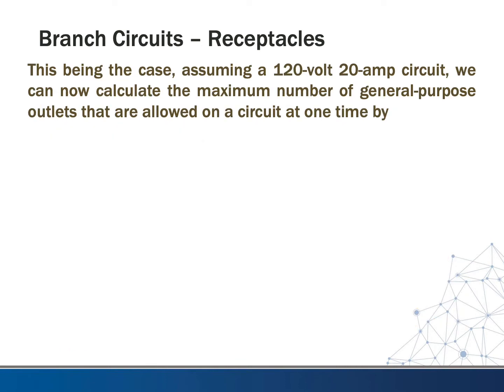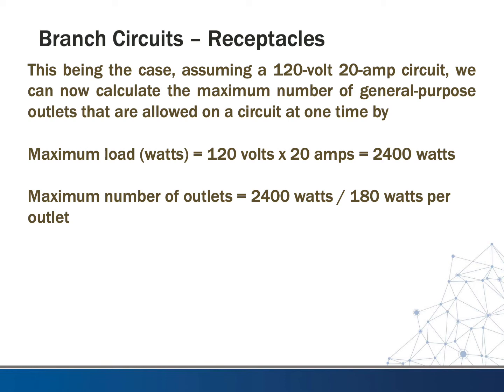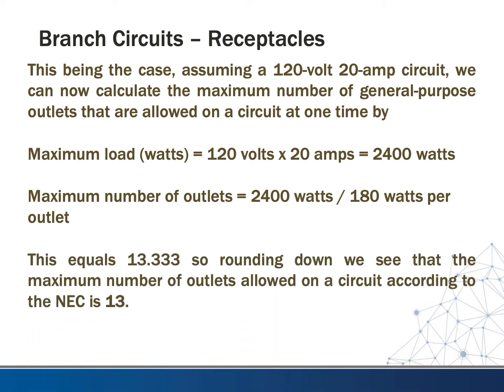Assuming a 120-volt, 20-amp circuit, we can calculate the maximum number of general purpose outlets allowed on a circuit. The maximum load on a 20-amp breaker is 2,400 watts. Since these are non-continuous, we can use the full rating of the breaker. Dividing 2,400 watts by 180 watts per outlet equals 13 and a third — so rounding down, the maximum number of outlets allowed on a circuit according to the National Electrical Code is 13.